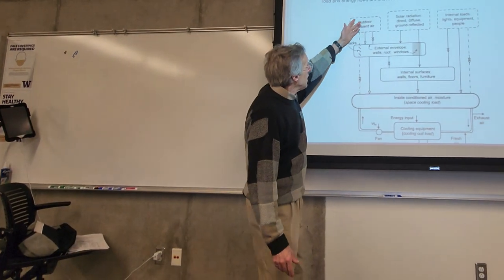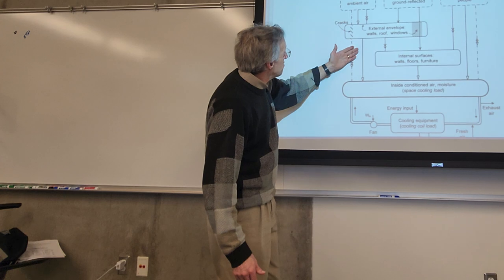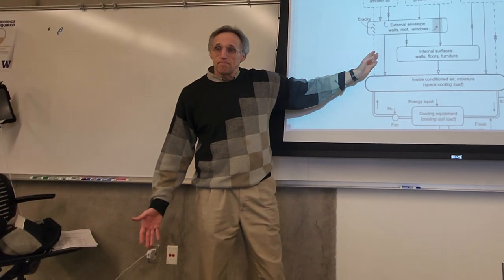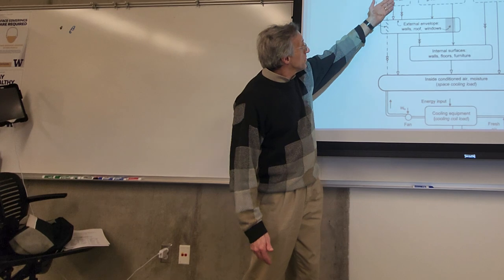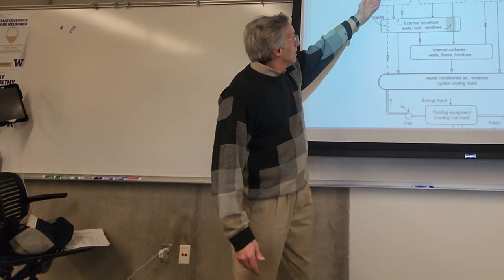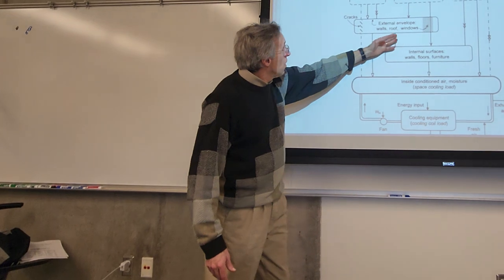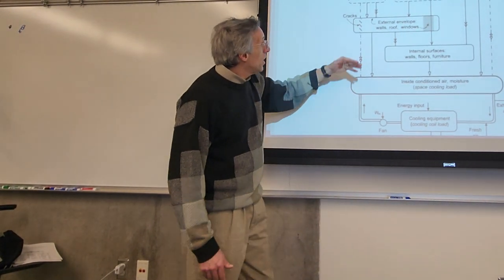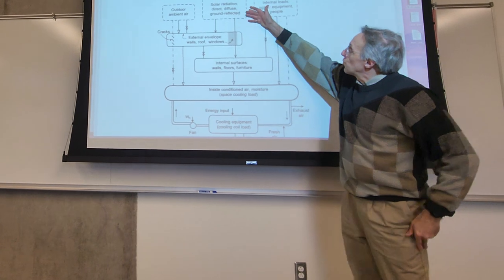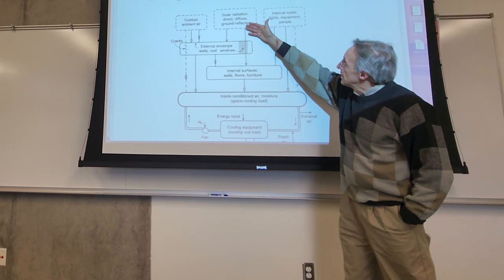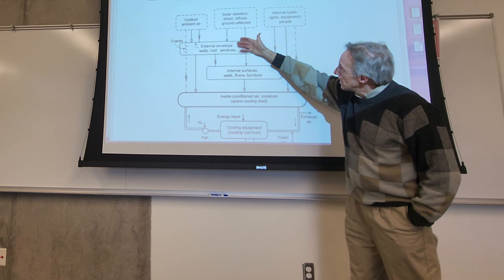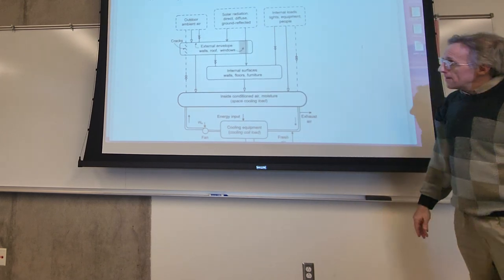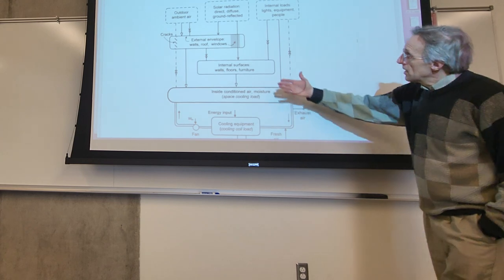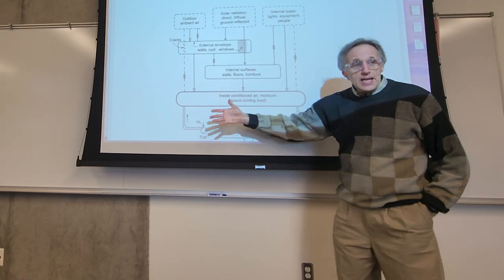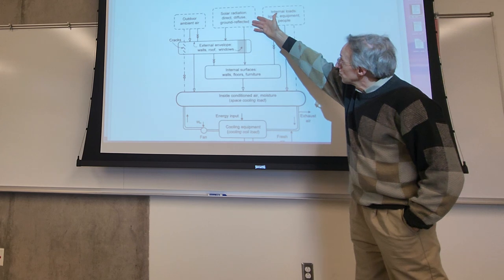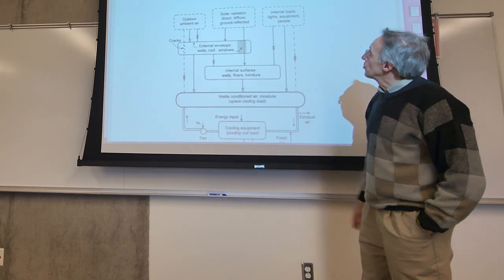There's the outdoor ambient air that is going to filter into our space by conduction in the summertime. In the wintertime, it's going to go out. This is a summertime mapping here. Heat comes from outside in through the walls and the windows and the roof. We have solar radiation: direct, ground reflected and diffuse coming in, especially through the windows. Some of that comes in as direct heat into the space, and other parts are absorbed in internal surfaces.